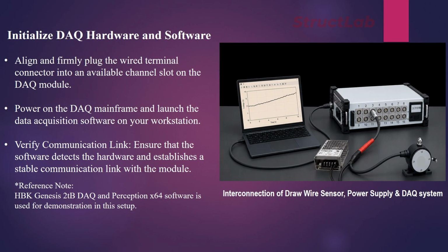Now that the physical wiring is complete, Step 5 is to initialize the DAQ hardware and software. Align and firmly plug the wired terminal connector into an available input channel slot on the DAQ module. Power on the DAQ mainframe and launch the data acquisition software on your workstation. Verify the communication link, ensuring that the software detects the hardware and establishes a stable communication link with the module.